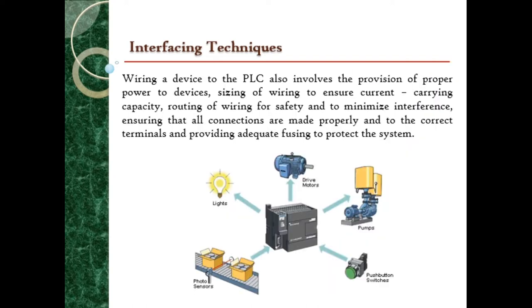So wiring a device to the PLC is very important because you may connect this PLC with a high current output such as motor drivers and pumps, or with lower current input devices such as a push button. But in doing these connections, we must make sure that these connections are safe, and that the routing of the wiring is safe to minimize the interference between these components and the PLC. And then we have to make sure that all connections are made properly and to the correct terminals, and provide adequate fusing to protect the whole system and the PLC system.